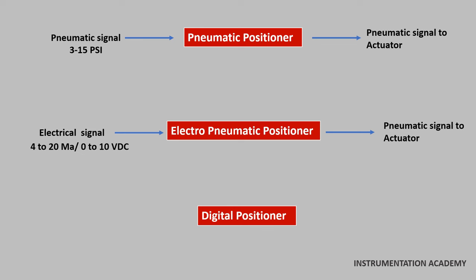A digital valve positioner receives an electric signal, typically 4 to 20 mA, HART, Profibus etc from a controller. It then sends a corresponding output pneumatic signal to a pneumatic valve actuator.